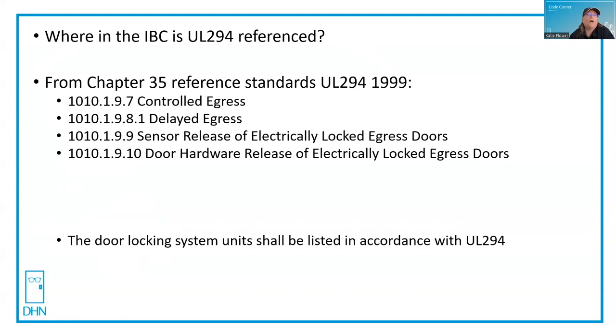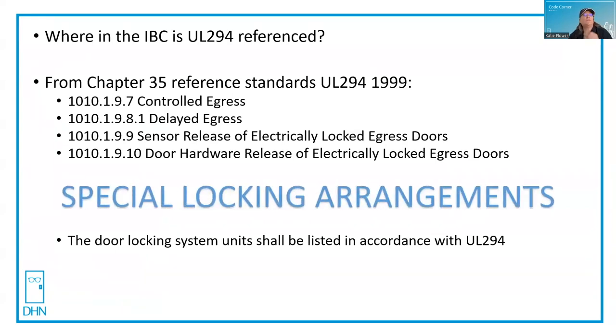What do these sections all have in common? They're typically using some kind of a mag lock or an electrified lock that locks the door on the egress side. In other words, these are special locking arrangements. The door locking system units shall be listed in accordance with UL 294 — every one of these has that as a listed criteria, and so the door locking system units are what needs to comply.